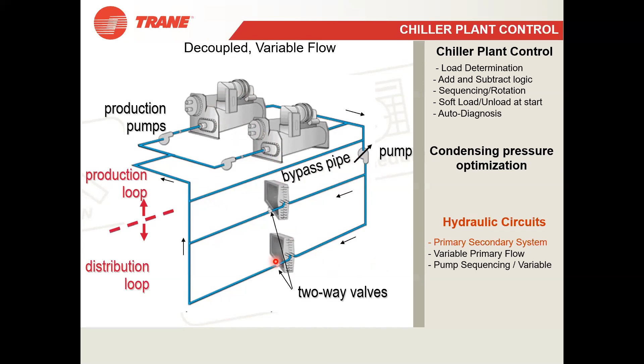describing different circuits. Actually, chiller plant control can use different kinds of circuits. The first one is the primary secondary system. So what is primary secondary? You know, there are primary pumps, secondary pumps, and there is a bypass line also. So what it will be doing actually, one minute. I think yes, this slide will be better to understand.